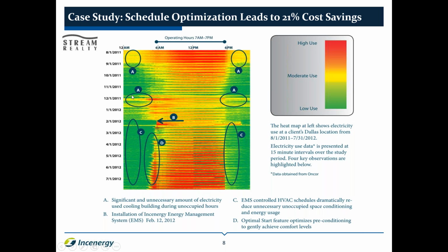What we're looking at in the periods marked with an A is high energy consumption prior to when the building is open. The building in this particular case is open at 6 a.m. and closed at 6 p.m. Prior to implementing our system, we were getting a lot of energy consumption before 6 a.m. and after 6 p.m., which was driving up energy costs. After implementing the system, we can see a very nicely defined cutoff before and after the building is open, so those periods of energy consumption are no longer present, which is largely responsible for the energy reduction.